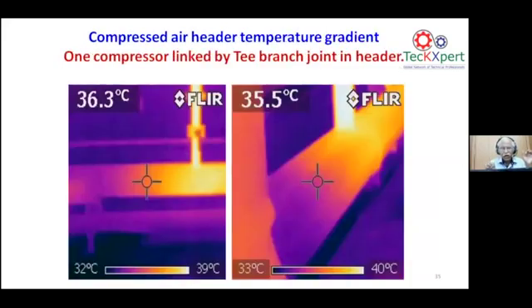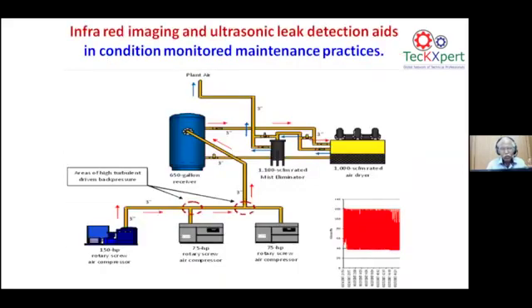We can see on the vertical side, one compressor is giving the delivery, and on the horizontal side, where you can see the cursor, this compressor is giving the delivery. So both the deliveries are having a clash and the turbulence of air is happening. Definitely, you can see the T junction is a loss to the compressor house as well as to the compressed air system. This has to be changed to conjoining bends. I will just show how the bends or the junctions are done. We can see I have imported this one image where it shows all the T junctions that are there in the compressor house. It is a point of turbulence, where the fluctuations in air pressure are more, and it's a cause of energy loss to the compressed air system.